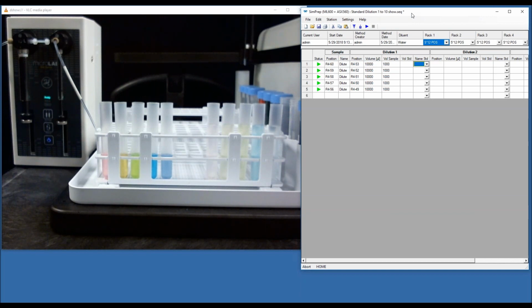Can the system be used with multiple solvents? That's something we're looking into. There's a hardware fix, but I think for most labs, the answer is yes, if you wanted to. The easiest thing to do would be, of course, you've got your solvent A bottle and you've got solvent B, and you just move the tube from one to the other, and then prime the system again before you start running samples. And then you've got a different diluent being used.